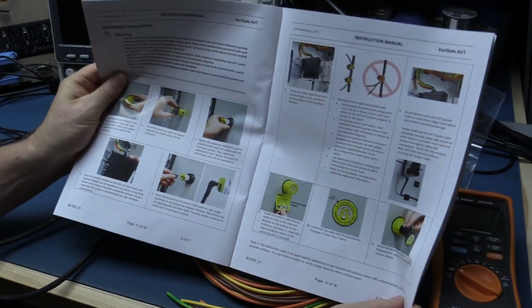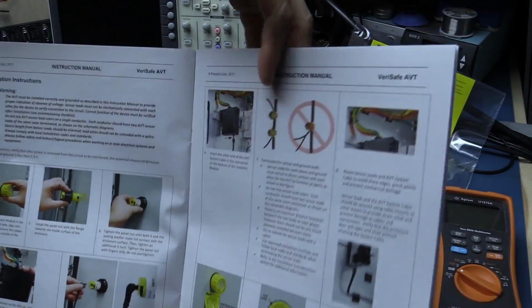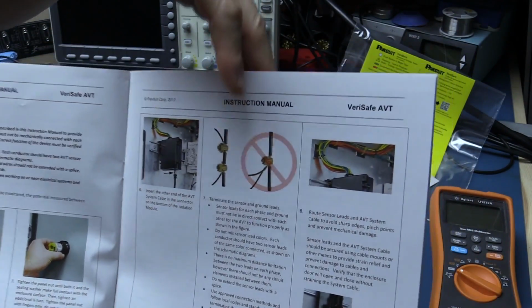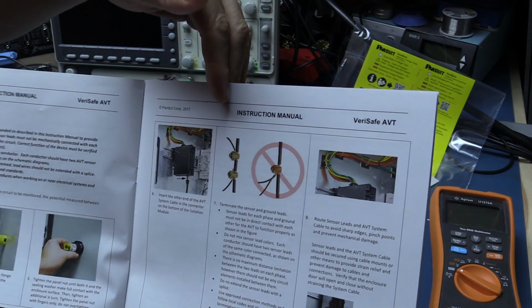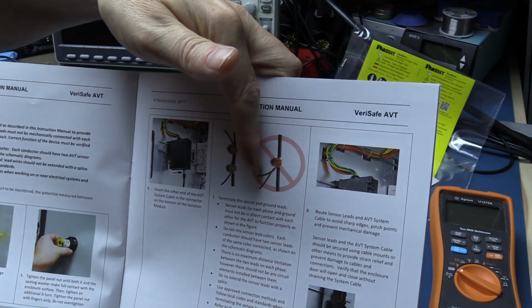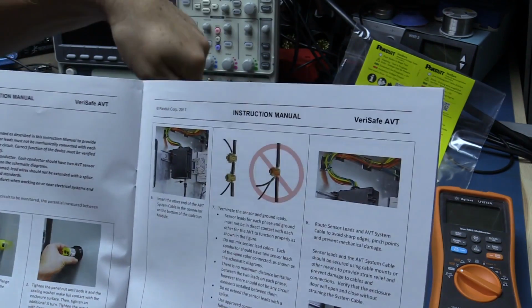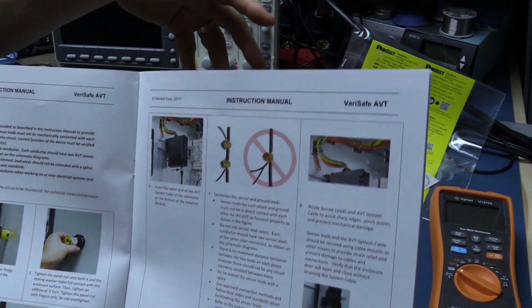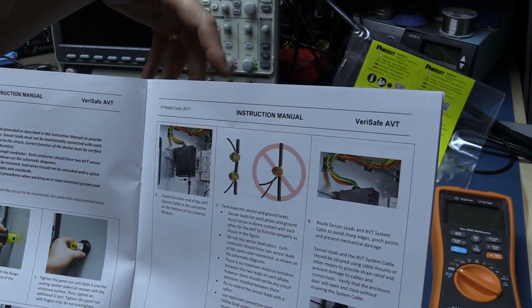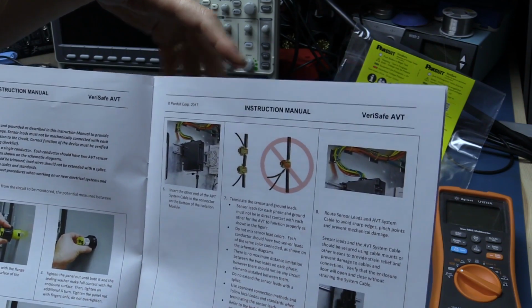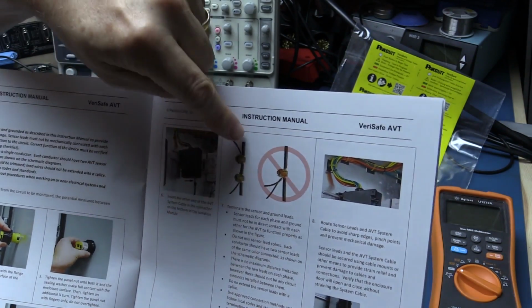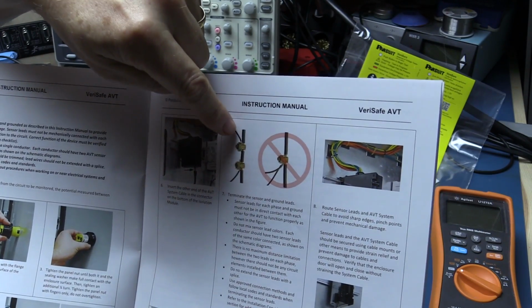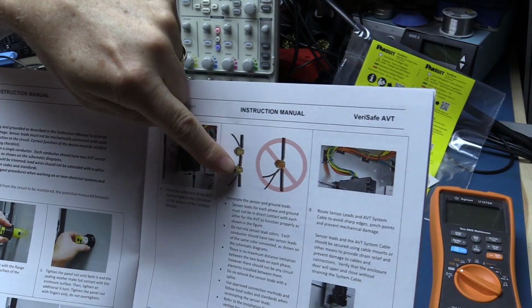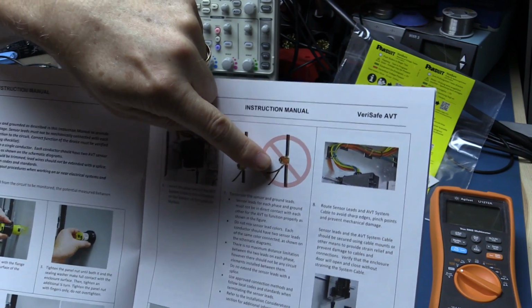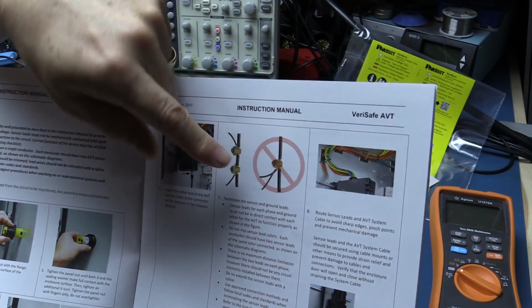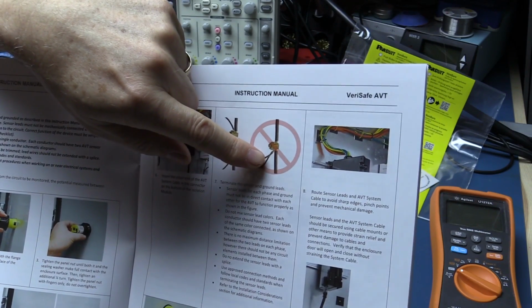A few instructions on how to wire it up. One important thing is this diagram - if you remember, each phase on the tester has 2 wires. You should not connect them both together into one termination point. I may do that just for testing because I don't have as many places to do this in a real world scenario. But the reason for 2 separate connections is to make sure that if the first connection falls out, the second one is still securely connected. If you've got them both on one terminal and that terminal comes loose and the wire drops out, it may think things are okay when in reality they're not.